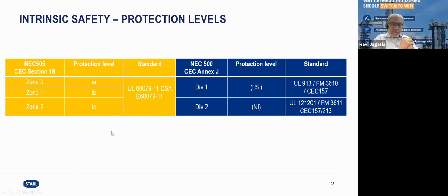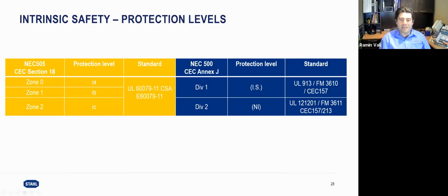Sure. If I understand the question correctly, when we have three Zener diodes, or we can tolerate two independent faults in a field device or in an associated apparatus, then it can be certified as EXIA, and it is suitable for zone 0. Now, if we are talking about NEC 500, which is intrinsically safe for divisions, we don't differentiate between IA or IB. We always should have at least two levels of faults to make sure that this intrinsically safe device is certified for division 1. So basically, that's how we are differentiating it.